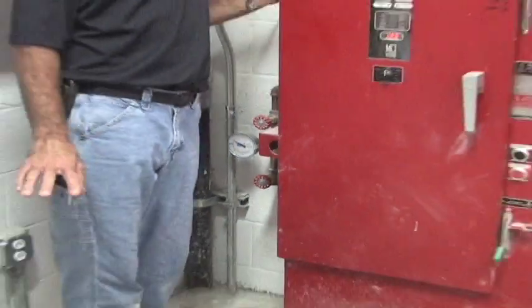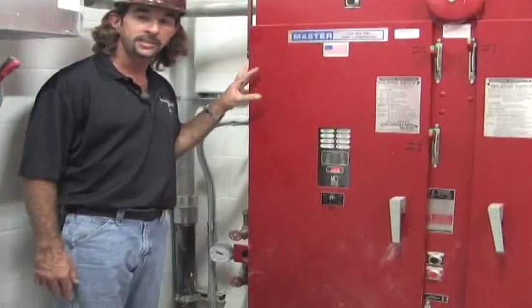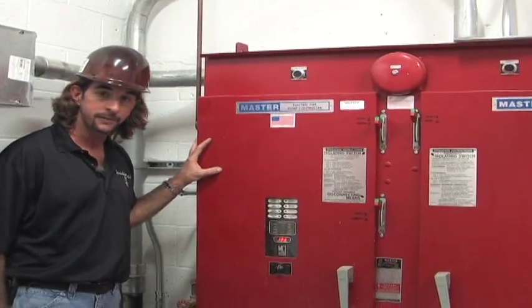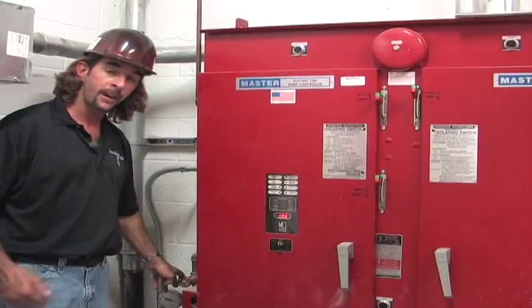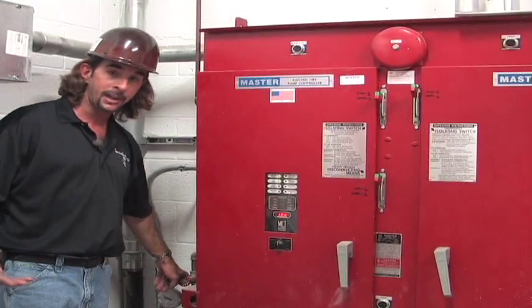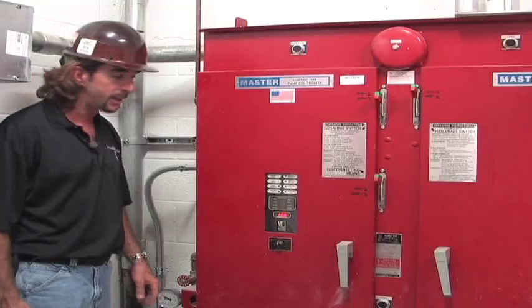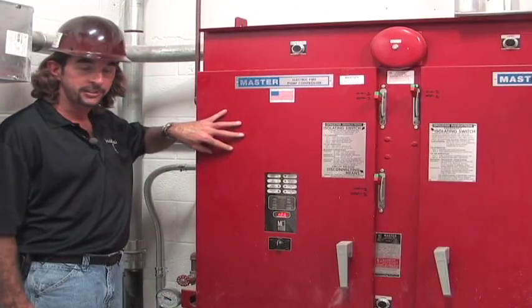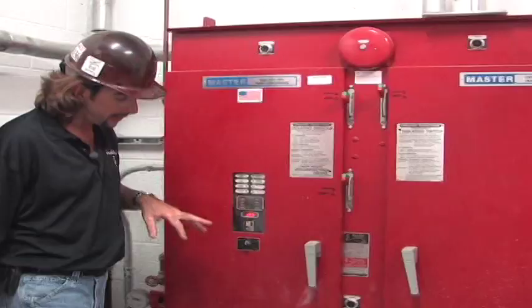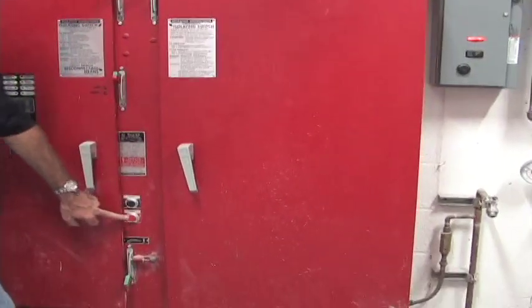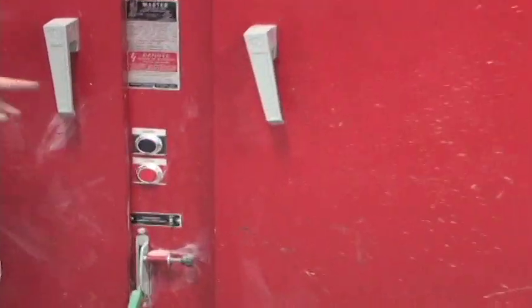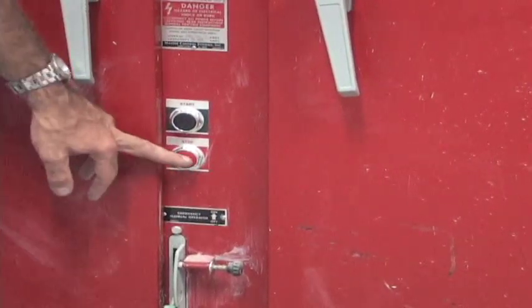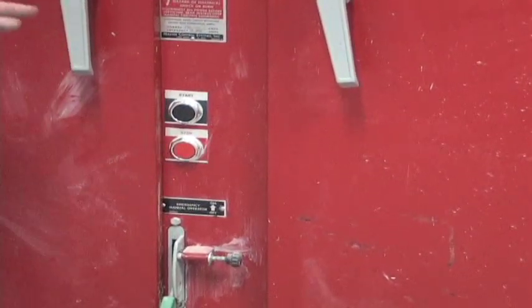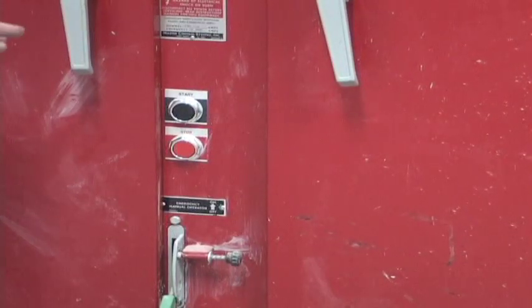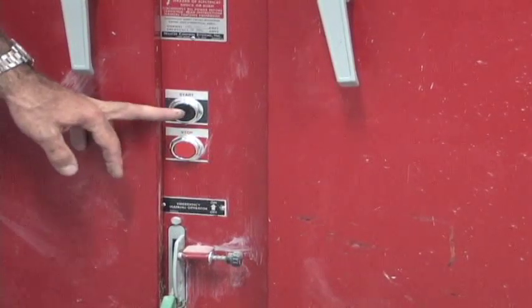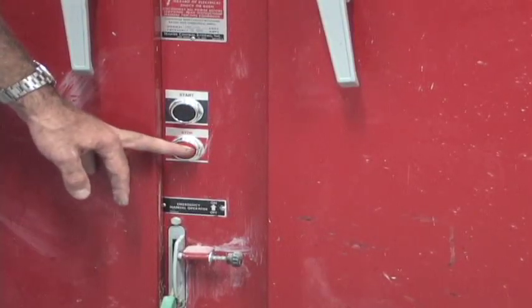Anytime the fire pump starts with the loss of pressure, the fire pump has a 10-minute run time and it'll automatically shut off. So with the loss of pressure, the fire pump starts. Once pressure is built back up to whatever building pressure is, 10 minutes later this fire pump will shut itself back off. If for some reason the manual start button was pushed, you would have to manually shut this off by coming back here to the stop button. So low pressure start, it'll shut off after 10 minutes once pressure is built all up. If you do the manual start, you have to manually stop this.